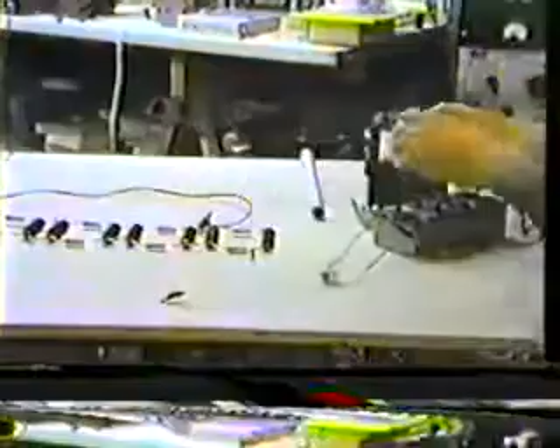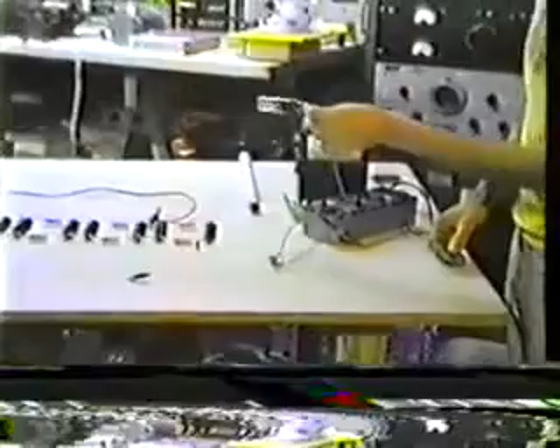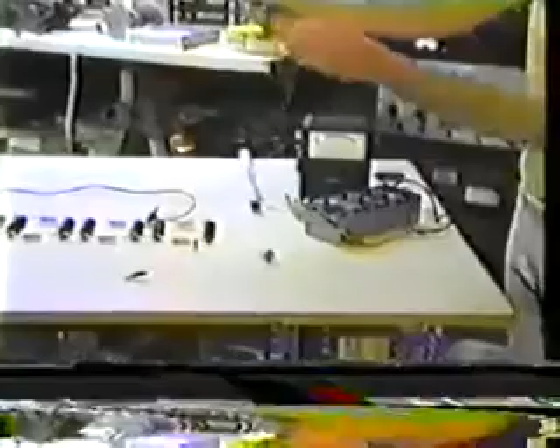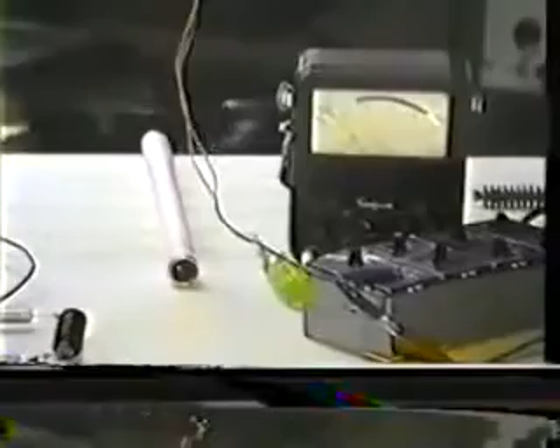Now what we're going to do is change our setup here a little bit. Connect this as a regular photo tube and remove our source of excitation. And if we can see, the Simpson shows that we got a slight response from the fluorescent lamp. You're right in front of the meter, so I can't show both. There we go. We got a little bit of response from the room illumination, which is pretty bright for the videotaping purposes. Now I'm going to bring the intensity of our apparatus up here to a point where we get some reasonable output.